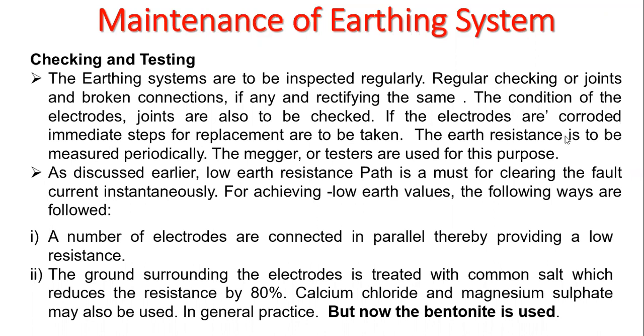Then the earth resistance is to be measured periodically. With the help of Megger, we can measure the earth resistance periodically. Then the next point is, as discussed earlier, a low resistance path is a must for clearing the fault current instantaneously. That means suppose any fault current occurs in a system, if your earthing resistance is low, it will pass that fault current easily. So how do we maintain low earthing resistance? For achieving low earth values, the following ways can be followed. In order to achieve a low earthing resistance value, we can follow the following methods.